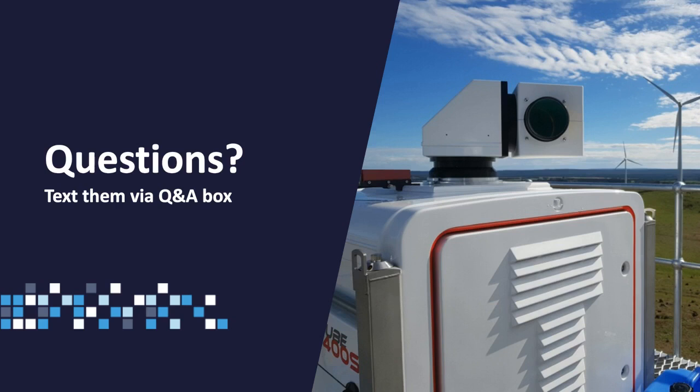All right. Thank you, guys. Go ahead. No, I was just saying that when we say measuring the power curve, it means fulfilling the requirement from the IEC. So having 180 hours of valid data and having enough coverage of the whole wind speed across the campaign. So that's what it means having a power curve.